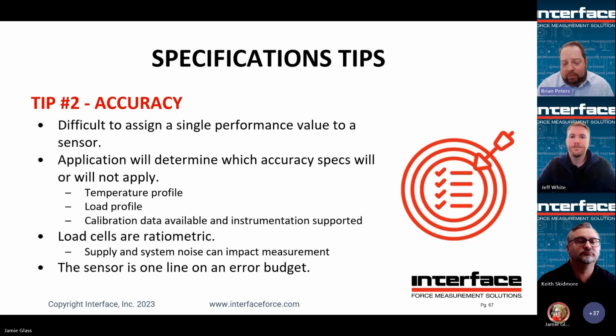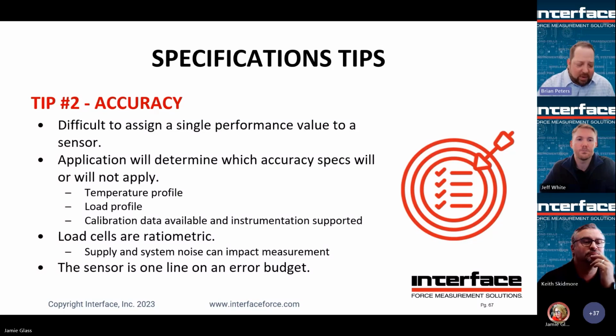It's going to come down to the temperature profile of the test. If it's constant temperature, good. You can move all the temperature stuff off the table. It also comes down to your load profile, like you heard earlier. If you're only doing a single ascending test, hysteresis, for example, doesn't matter. What calibration data do you have? If you have either your specific load point, or the curve data, then you can take out maybe nonlinearity, even hysteresis again, from impacting your measurement.